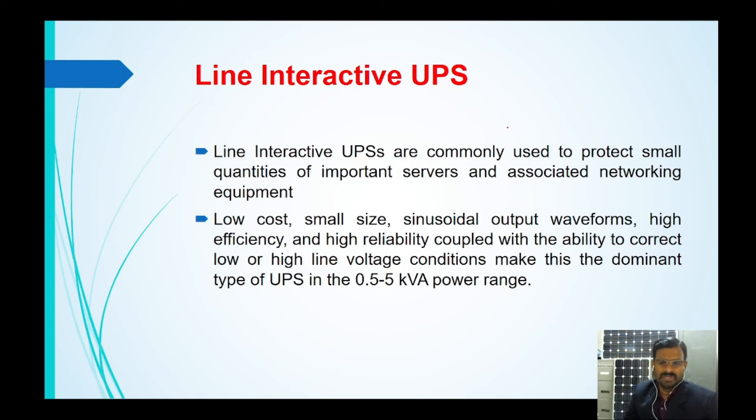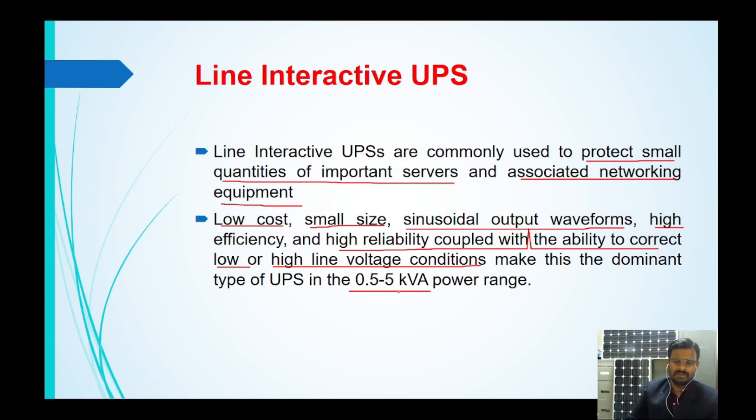Line interactive UPS are commonly used to protect small quantity of important servers and associated networking equipment. These are low cost, small size devices that provide sinusoidal output in both utility supply and stored energy mode. It provides high efficiency, high reliability coupled with the ability to correct low or high voltage conditions. This type of UPS is mostly used in 0.5 to 5 kilo volt ampere range.